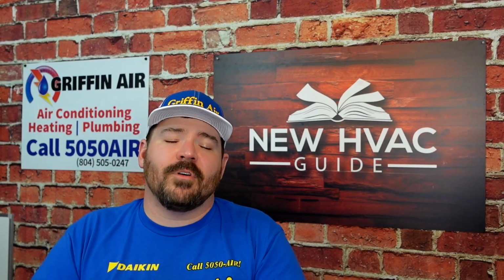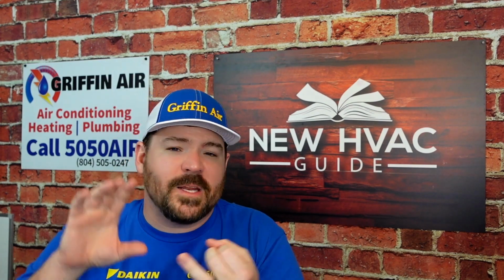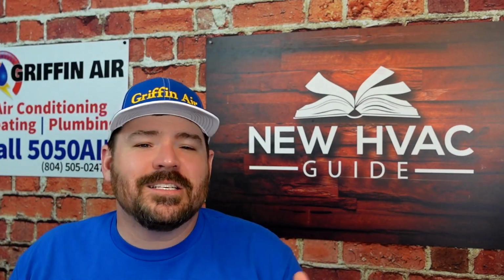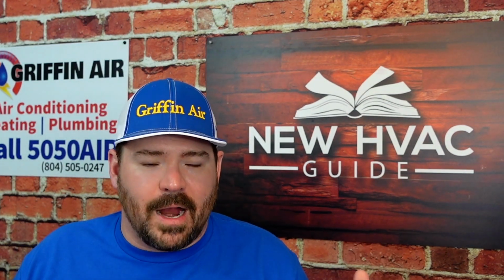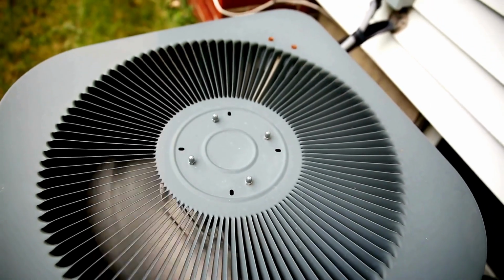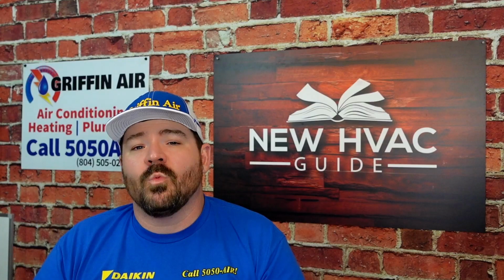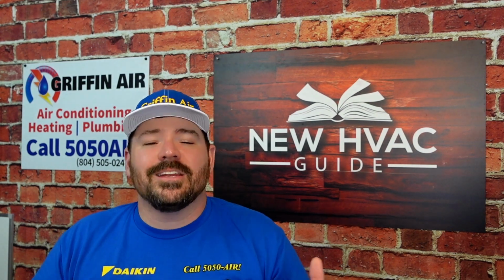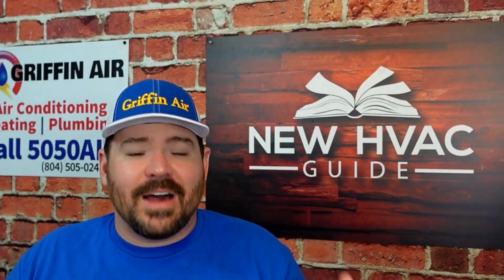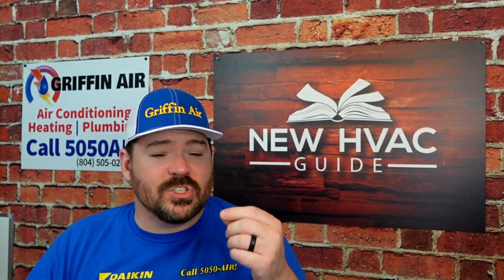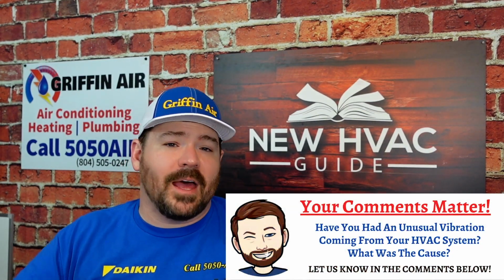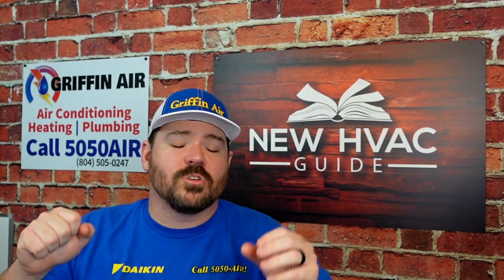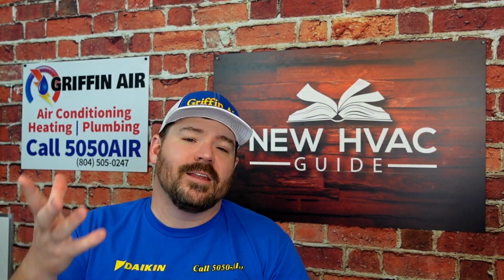And then finally, number five, something has come loose or has been installed in a way. Let's be honest, these systems are going to vibrate a little bit, right? With moving components in there, the system might develop some sort of movement or vibration, right? When installers are not keeping that in mind, it can cause you to be disturbed by the vibrations. When in reality, if the systems were installed properly, keeping things in mind like, let's make sure that furnace isn't right up against that joist, or let's make sure that it's hung in a manner that it has anti-vibration technology, or maybe some rubber feet under that furnace. Whatever you've got to do, keeping in mind that things do vibrate.